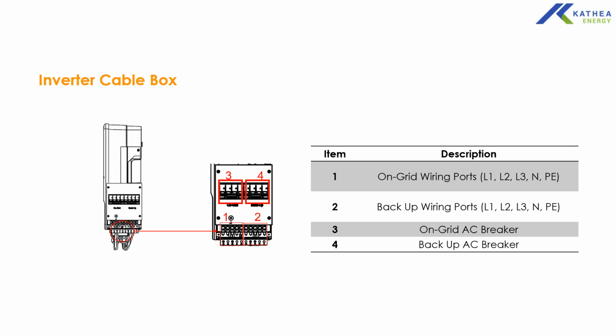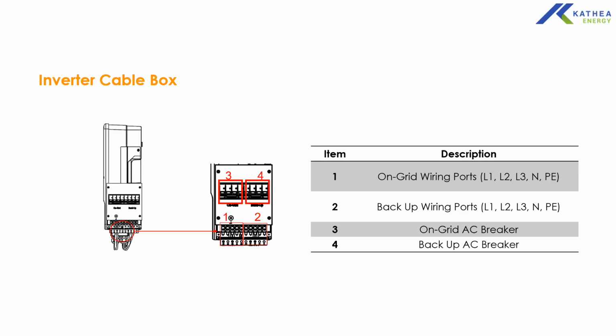Make sure your system is properly grounded. If not, it will report an isolation fault. So the system comes with all the isolation devices pre-installed. All you need to do is pull your wires from your strings or from your grid and to your essential loads board.